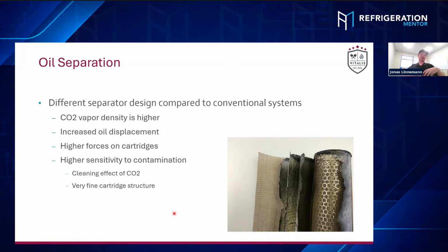So what we know from F-gas or ammonia, that we have centrifugal oil separators and stuff like that, is not really applicable to CO₂ at these pressures. So that's why these coalescence cartridges came into place with the transcritical CO₂ systems. And the thing here is the coalescence cartridge is a very fine mesh. It's pretty much the finest mesh inside the system, so it catches all the fine debris which is traveling through the whole system.